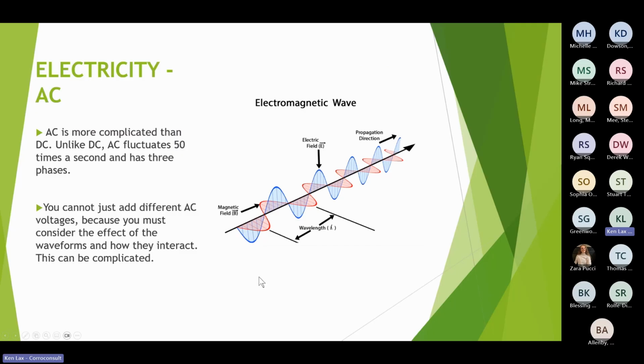to anything else. But the important thing to remember about these varying waves is that they're invisible. You can't see them, and there is an inviolable law that says if you have a conductor in a changing magnetic field, it will induce a voltage in the conductor. So although you can't see it, you could be near a structure that's getting electricity induced in it because of these fluctuations. And the magnitude of the voltage that's induced is proportional to the current and to the rate of change. So a rapidly changing field will induce more of a voltage than a slowly changing field. And the higher the current, the greater the induction.